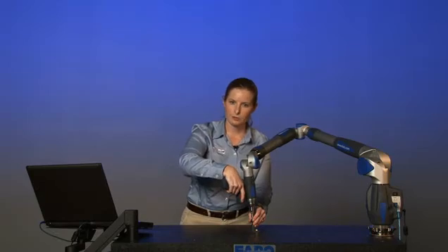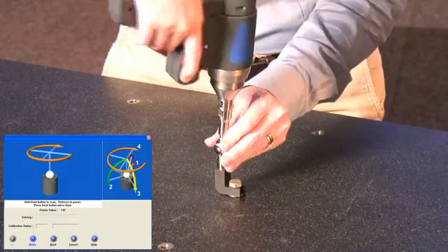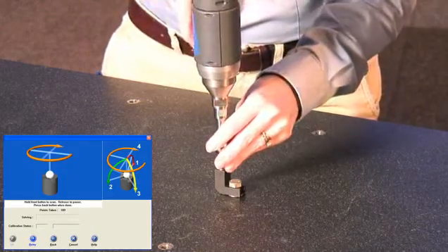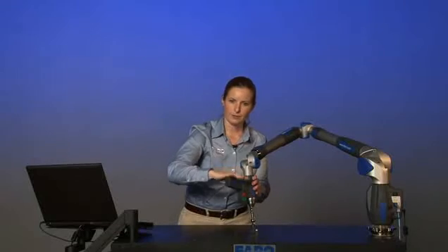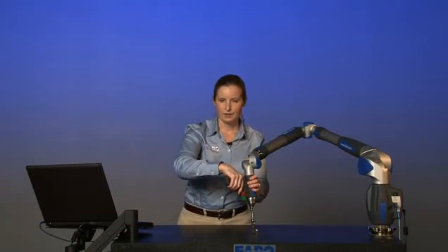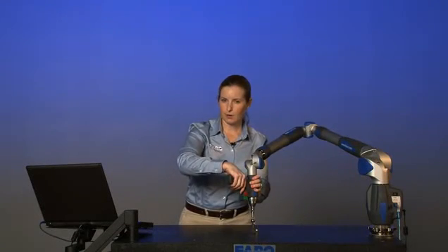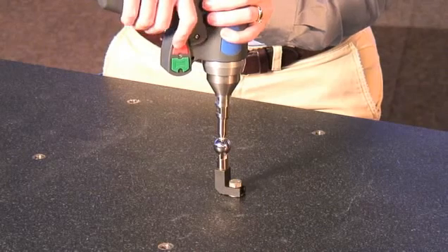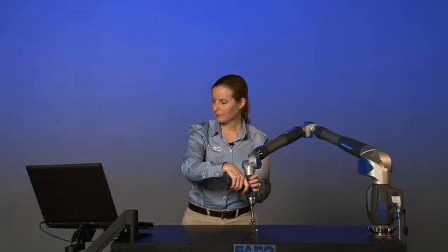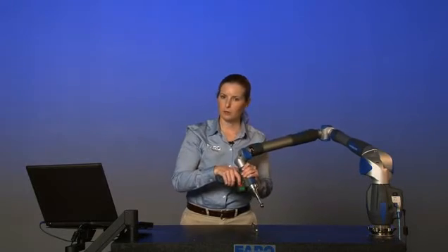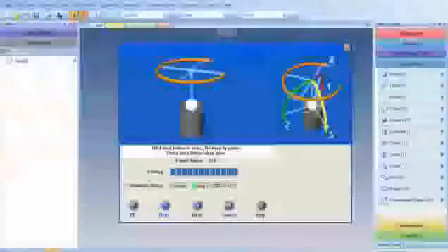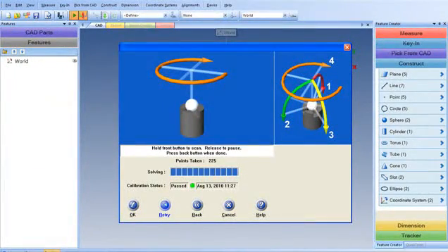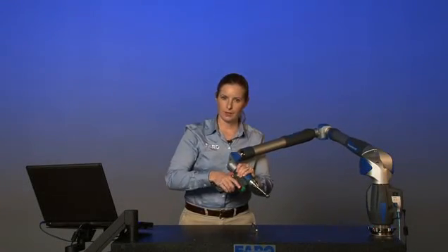Come up to vertical. And then if you're using a 7-axis arm, take one more sweep of the handle axis. Now that we've had all the points that we need, press the red button. And you can calculate whether your probe calibration passed or failed. We've got a passing calibration, so we're ready to measure with the arm.